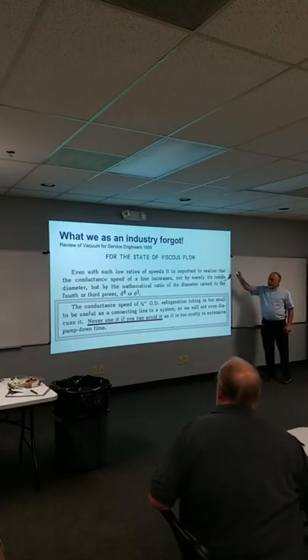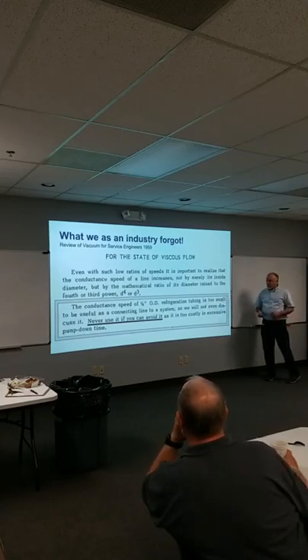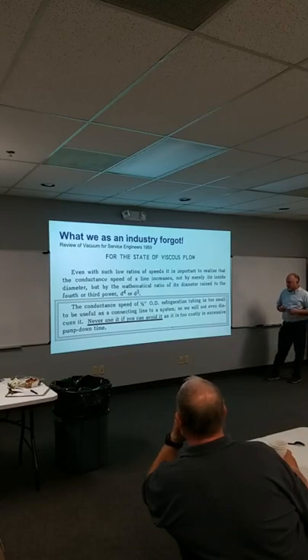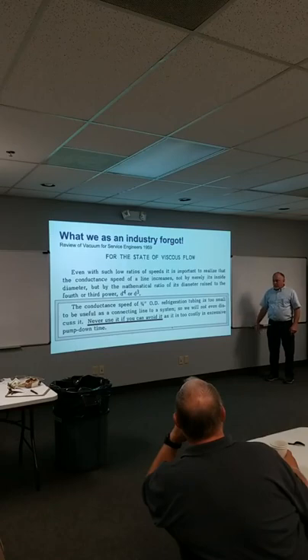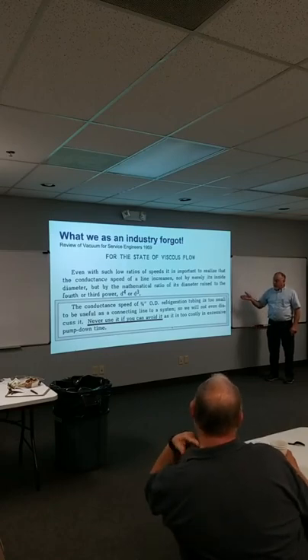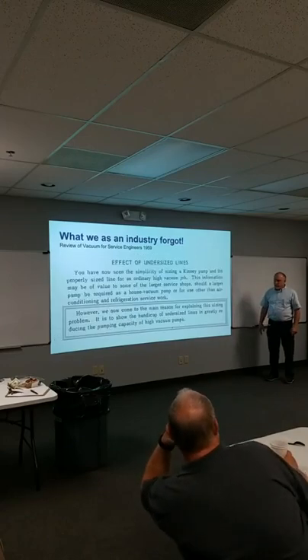1959, right? And this is like, how the hell did we forget this as an industry? And it goes down here, I got highlighted here. The conductance speed of 1/4 inch OD refrigeration tubing is too small to be used as a connecting line in the system. So we'll not even discuss it. Never use it if you can avoid it, as it's too costly and causes excessive pump down time. Right, so it's literally 1/4 inch service line we're talking about here. And when they wrote the book on vacuum, they're saying never ever use this. We're not even going to talk about it, it's stupid, right?